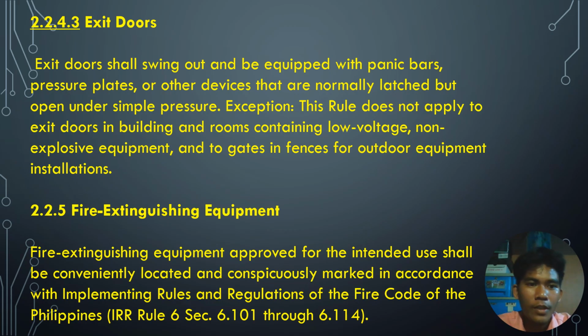Exit doors. Exit doors shall swing out and be equipped with panic bars, pressure plates, or other devices that are normally latched but open under simple pressure. Exception: this rule does not apply to exit doors in buildings and rooms containing low-voltage, non-explosive equipment, and to gates in fences for outdoor equipment installation.